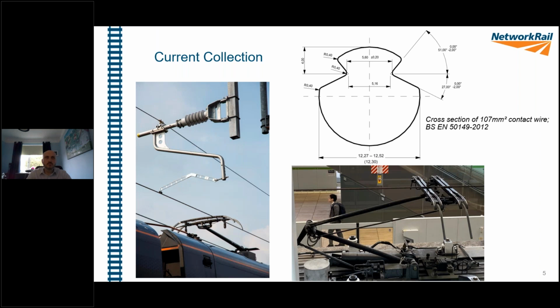Other things to note is that any incorrect installation or alignment of the overhead line can very much affect the overhead line geometry here. So if the contact wire was too far to the side of the pantograph, we will typically get a failure mode known as side wear, which is an accelerated form of wear on the contact wire, which typically leads to premature failure and dewirements, which are not so great.